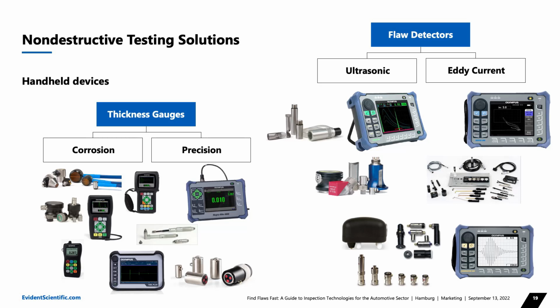The other product segment is flaw detectors. Here we have two types: ultrasonic flaw detectors and eddy current flaw detectors. Those are open instruments, so you can set up a big panel of different applications and use different probes for a specific need. For instance, eddy current is used in automotive for conductivity measurement, material sorting, and crack detection, and ultrasonic can be used for looking inside the volume, detecting corrosion, voids, cracks, and welds.